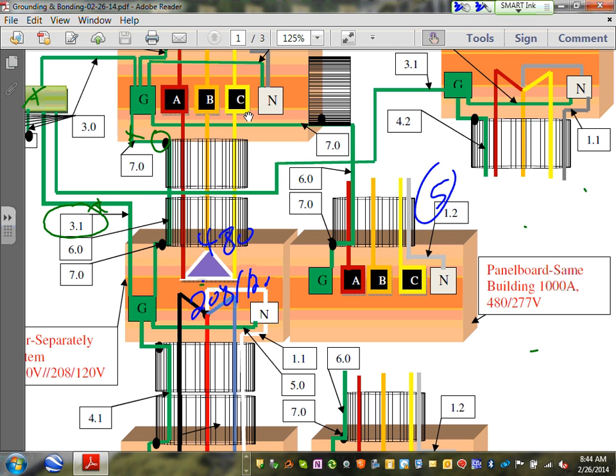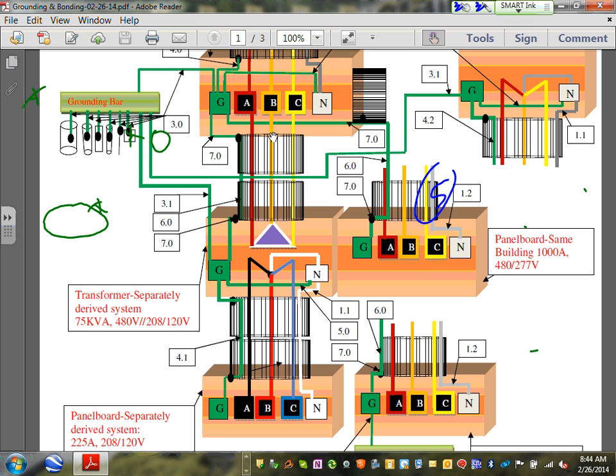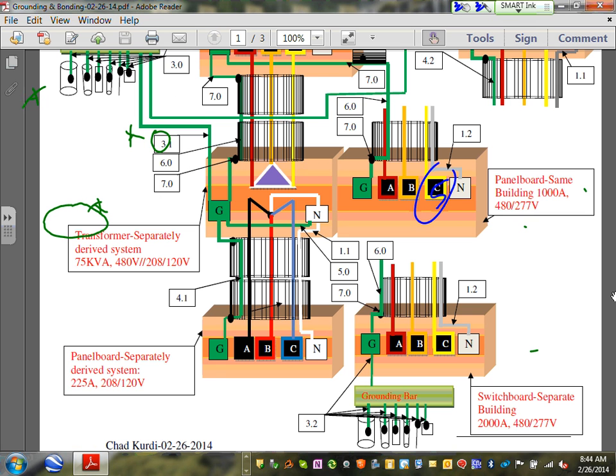Okay, when you are in the separately derived system, gentlemen, which you are right now, let me zoom a little bit. It's called a separately derived system, no connection between the primary and the secondary. The first thing you need to do is bring a grounding electrode conductor, which is that guy right in here, and take it to the ground bars right in here, to the grounding electrode system. That's a must by code. Then the second thing that you need to do is you need to have this guy.